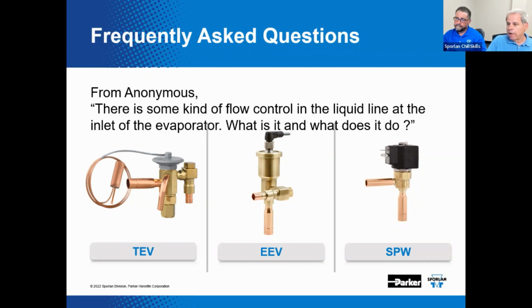This thermostatic expansion valve has a removable strainer assembly. You can access that if you remove the valve from system pressure, or isolate it from system pressure. Likewise, this EEV has a similar component. You can remove this inlet strainer, clean it, and replace it, and that's a real good service attribute of these two styles of valves.